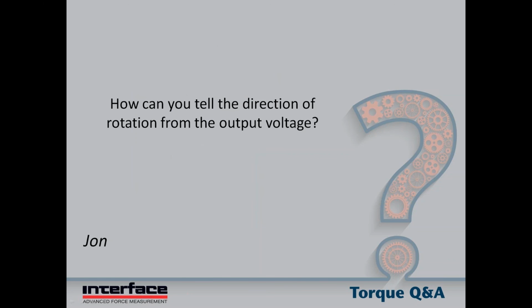Next, how can you tell the direction of rotation from the output voltage? That's a very good question. In fact, it comes up fairly frequently. The output of a torque sensor, just like a load cell or any strain gauge sensor, is very typically going to be bipolar, which means the output reverses polarity as you cross through zero in your measurement. That really has absolutely nothing to do with the direction of rotation. It really only has to do with the direction of the torque. So say if you're slowing down a rotating system, for example, the torque very well may reverse, and that'll happen before the system stops. And eventually the reverse torque will cause the system to stop and then start spinning in the opposite direction, but it definitely lags the actual direction in many cases.